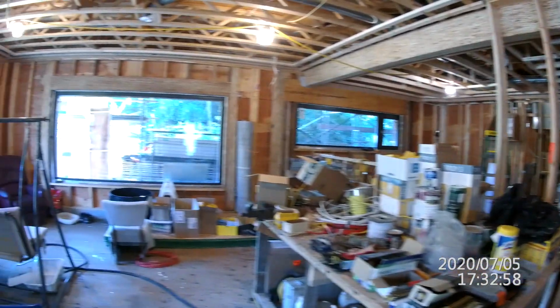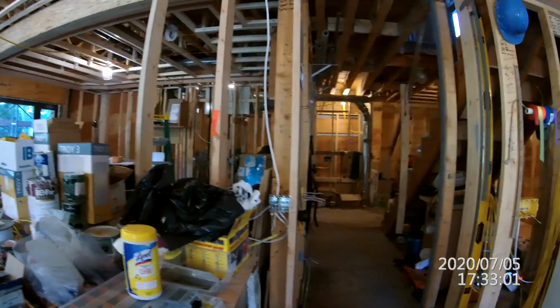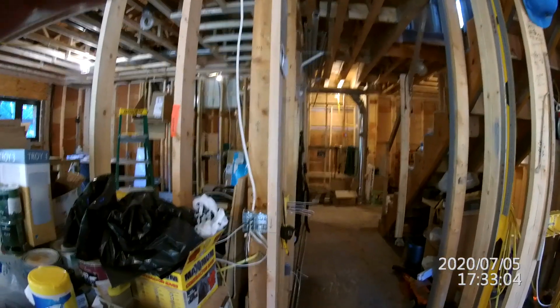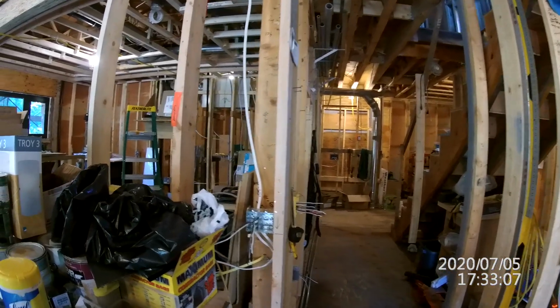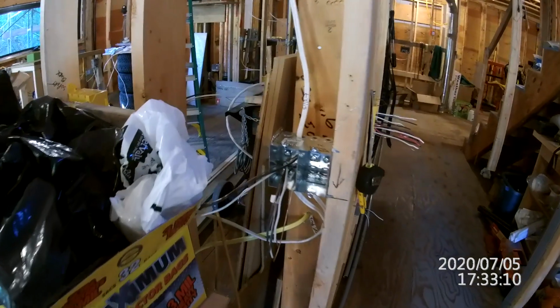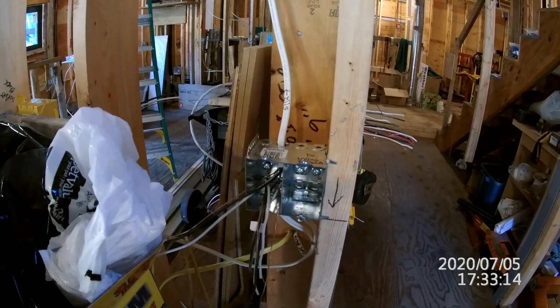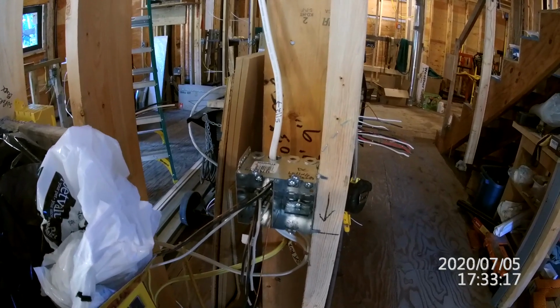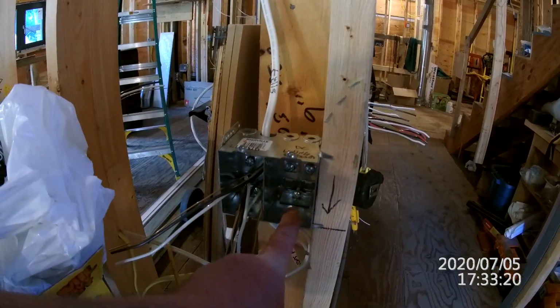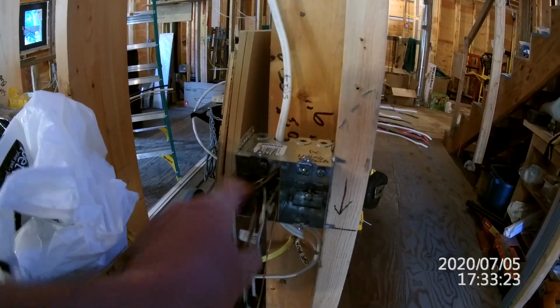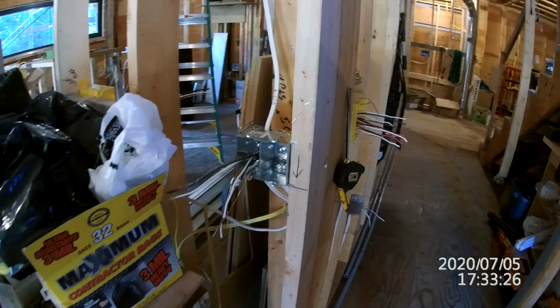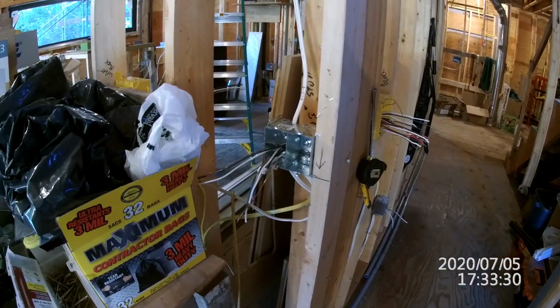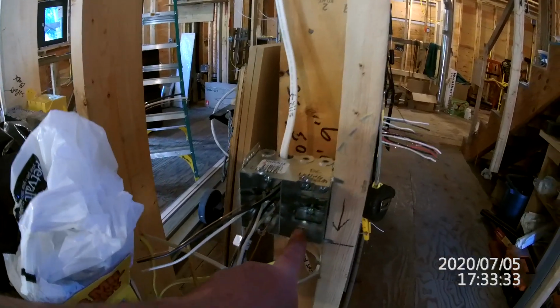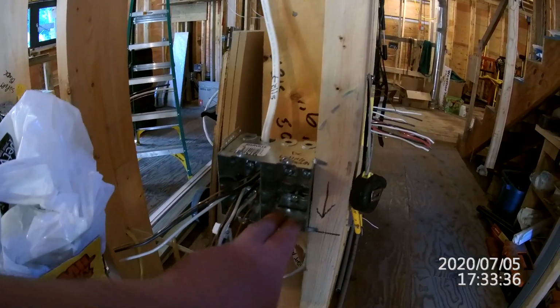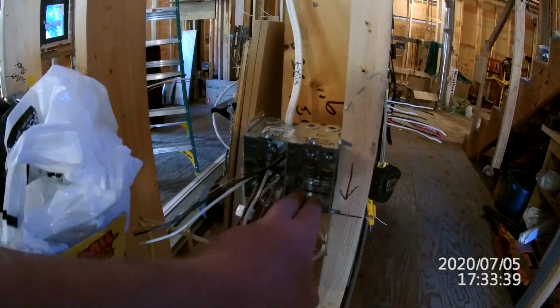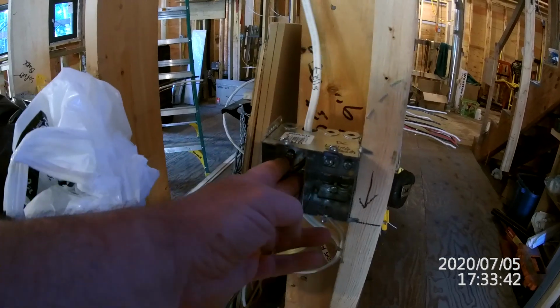Basically, it involved rethinking how I did the electrical boxes. For instance, here's a box that used to be a 2-gang plastic. But to do class 1 wiring, you have to separate the low voltage DC from the higher voltage AC, and that made things a lot more interesting, because even though this is only going to have 4 conductors in it, I can't borrow the excess 2 conductors allowed to service this side of the bay.